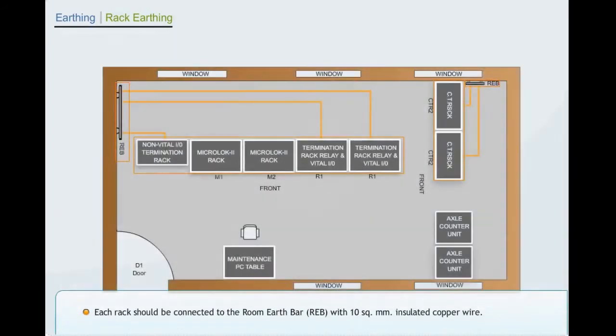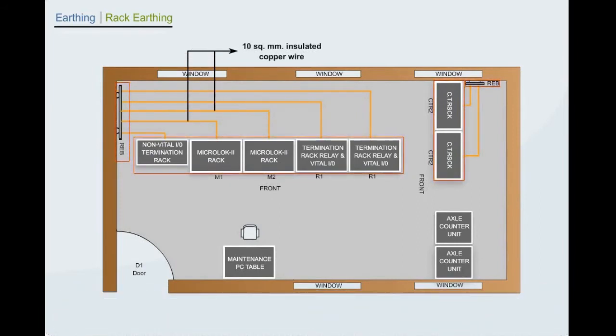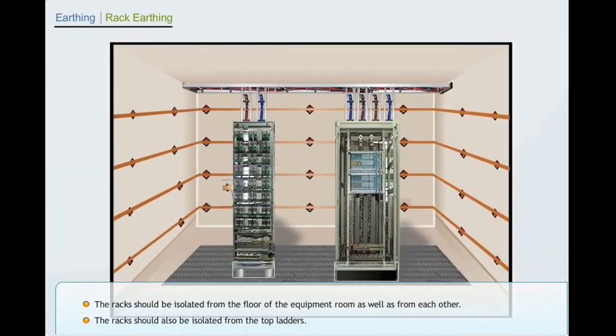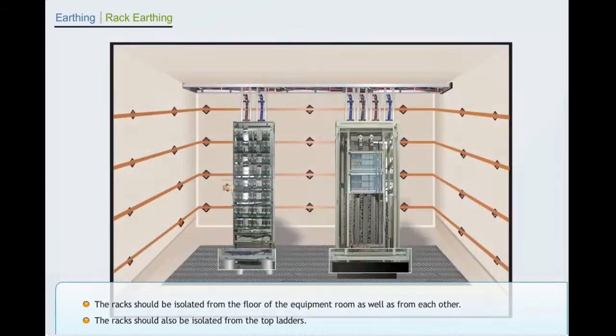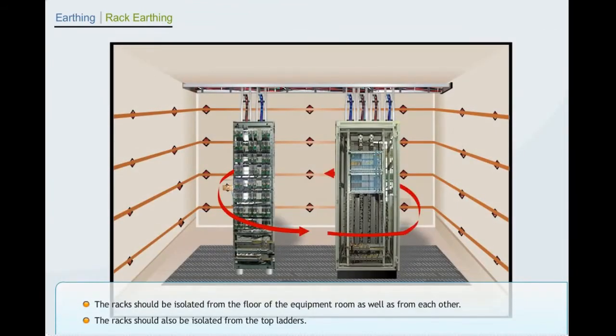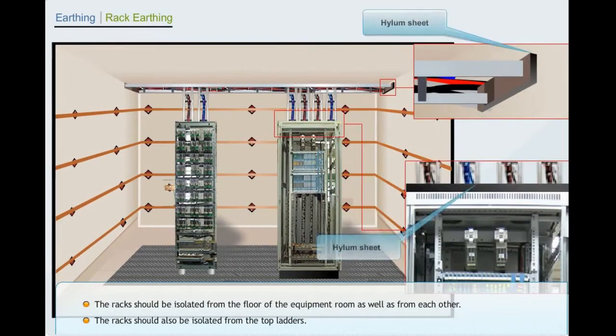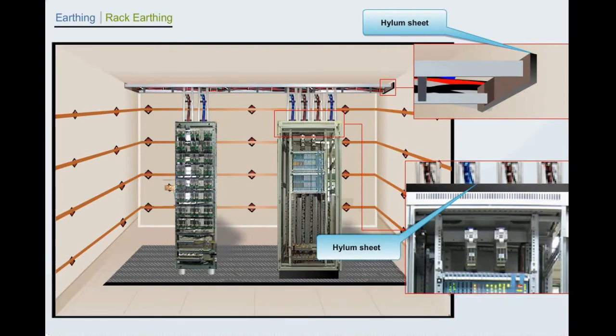Earthing, rack earthing. Each rack should be connected to the room earth bar with 10 square mm insulated copper wire. The racks should be isolated from the floor of the equipment room as well as from each other. The racks should also be isolated from the top ladders.